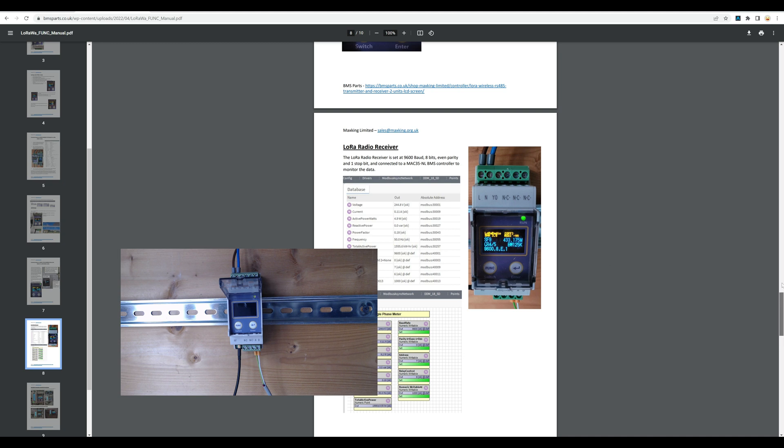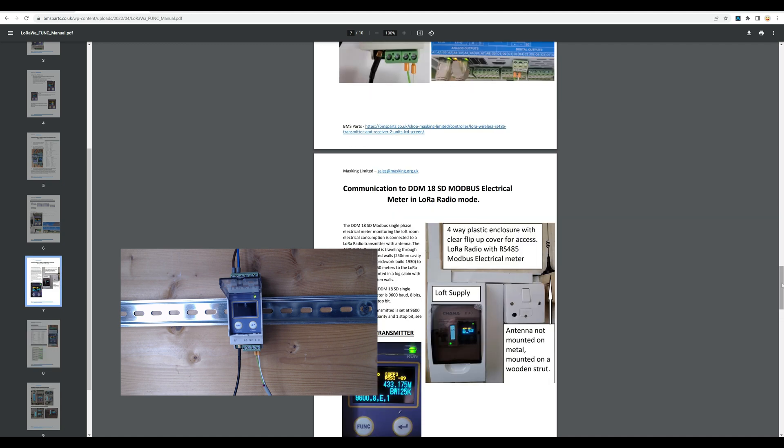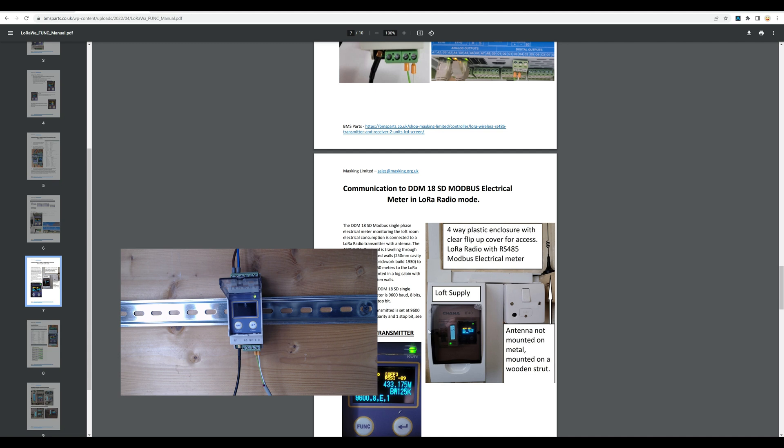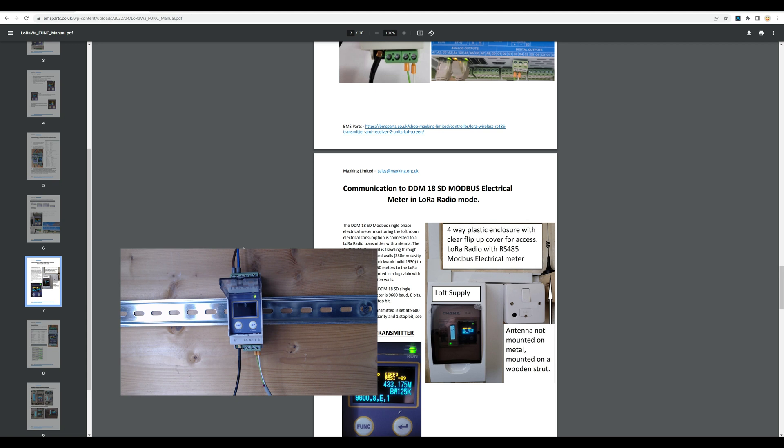There is something to note with this. The installation. See this antenna, it's got... we normally stick to a metal cabinet or metal base, but this is on a wooden strut. So there's no ground plane, and it's still communicating that distance. That's a good distance considering it's in a cupboard, a double brick wall, not a plasterboard, double brick wall, then another double brick wall to the outside with insulation. Then I would say 25 to 30 meters to a log cabin with 150 millimeter thick wood. And it's going through there.